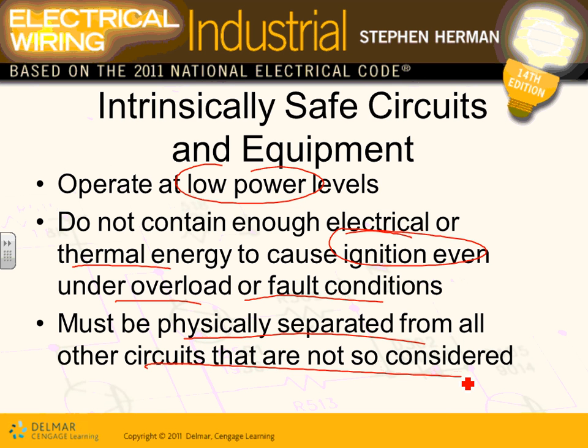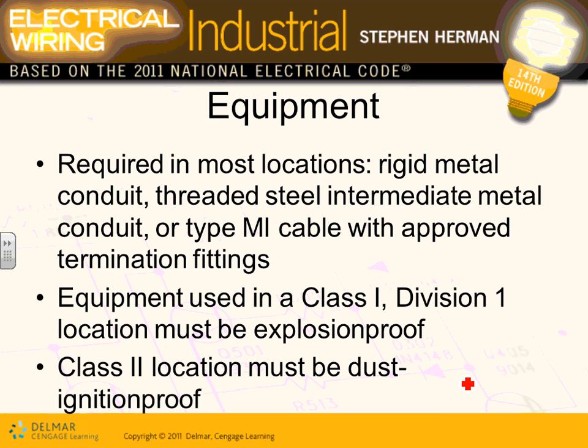Imagine there's a petroleum refinery. Can you imagine how many sensors are there to sense what's going on in that plant? If these sensors were not intrinsically safe, they would have to be put in rigid metal conduit and a lot of other things. So they created that system, a control system where, if you spark, it doesn't spark. Any comments about intrinsically safe systems? Put them in a blue conduit, label them intrinsically safe, separate them from all the other systems, and they're used for sensing only: instrumentation, monitoring what's going on in the system, and signaling. So that's your intrinsically safe system.